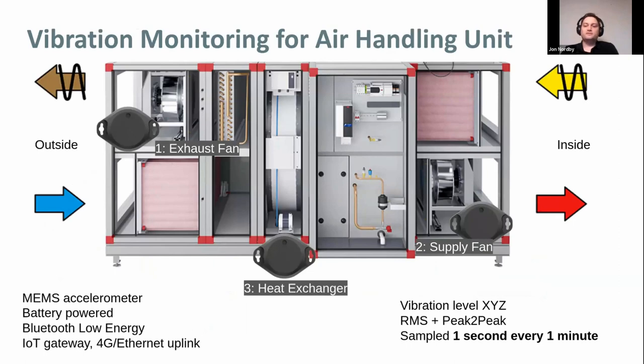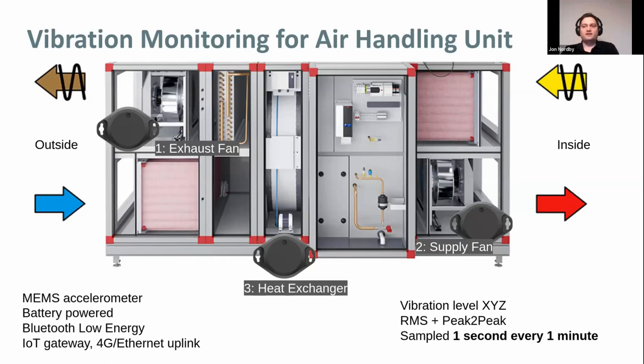We use vibration monitoring with wireless sensors equipped with MEMS accelerometers that are battery-powered and transmit their data over Bluetooth Low Energy. They transmit data to an IoT gateway, which communicates it to the cloud using 4G or Ethernet. The sensors measure vibration levels in X, Y, and Z, and transmit both mean and peak vibration levels. This is sampled for one second every one minute, giving a rich source of data about these components.